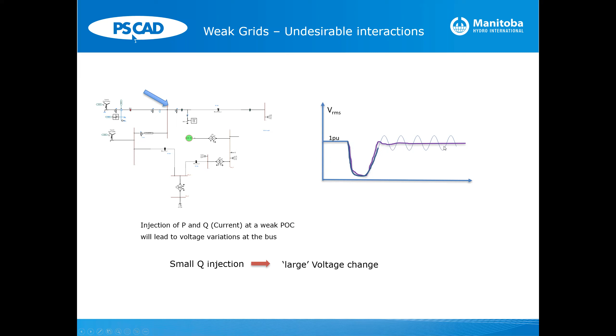Now, this was a practical case where there was a developer who wanted to connect a solar power plant to this weak point, okay? And there are two transmission lines, and one of these transmission lines tripped. What happened is we found that the system goes through unstable interactions. So the PV plant and the battery, because they're connected in close electrical proximity, both try to control the voltage at the common point. And essentially they started to have a hunting effect whereby they're fighting to control the voltage. And so the system had undesirable interaction.